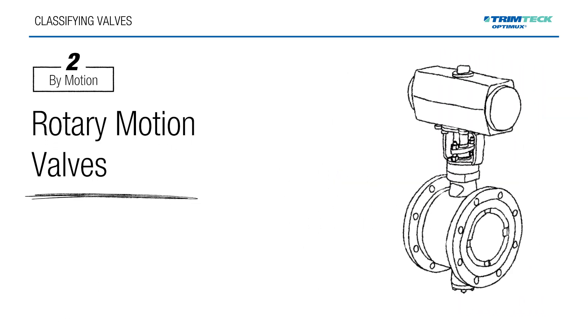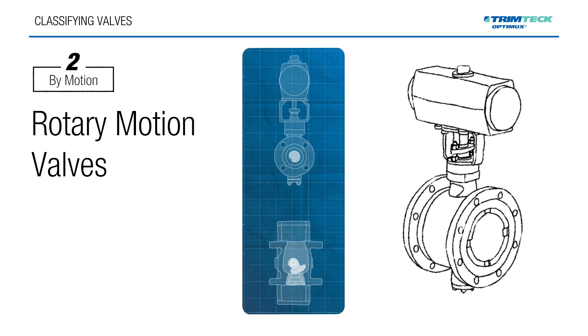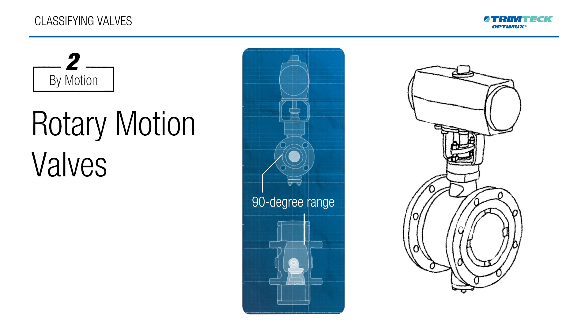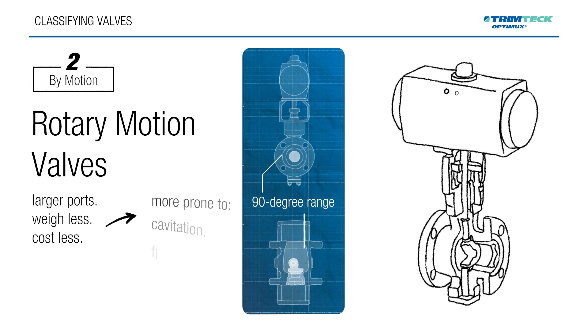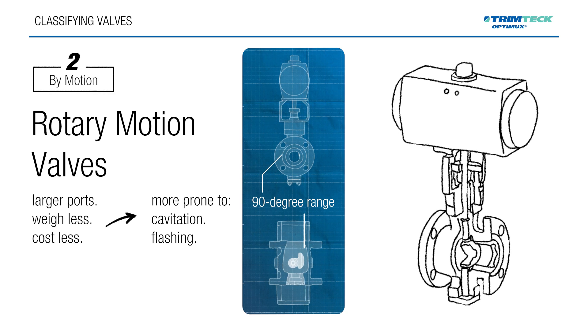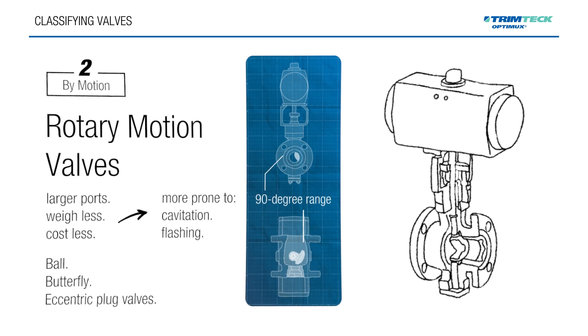Rotary motion valves use a closure element that rotates, usually within a 90-degree range. Compared to linear valves, they often have larger ports, weigh less and cost less, but they can be more prone to cavitation and flashing under high-pressure drop conditions. Common rotary valves include ball, butterfly, and eccentric plug valves.